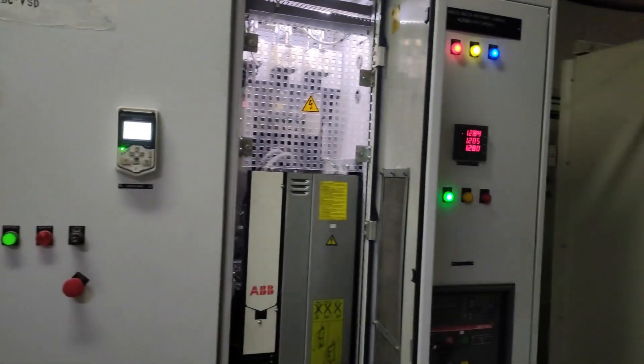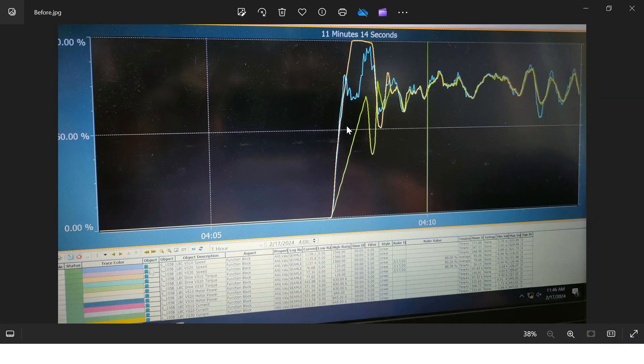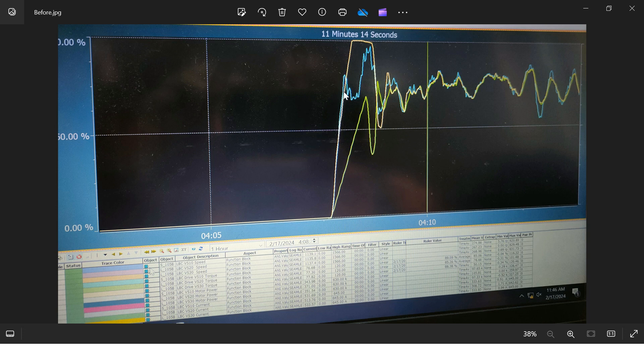Looking at the diagram, I have shown three trends for the three drives — that is the torque. You can see speed, torque, power, and current. But for understanding, I have shown only torque here. The orange trend is for the master, VS30; this is VS10 and this is VS20. You can see VS20 is taking the torque very slowly. That's why the other two motors are taking high current — most of the load is carried by those two motors, and that's why the current is high and it is tripping.